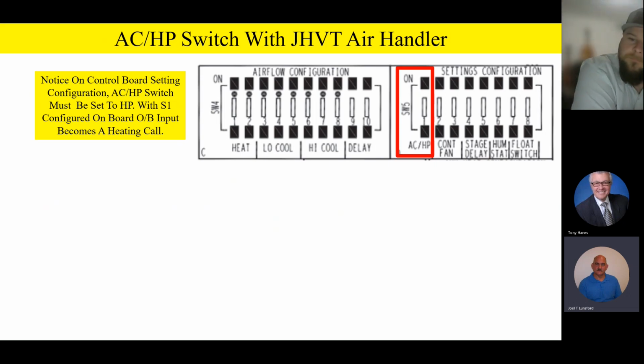Now you're going to notice on the control board that the AC/heat pump switch must be set to the HP position. This is important because when you have an S1 input on the board, it's going to look at that dip switch to make sure that it's on a heat pump. So you want to make sure that on the control board itself, you're setting up the air handler to know it's looking for a heat pump. Then with an S1 input or an S1 configuration on the board, that O/B input from the thermostat becomes a heating call.